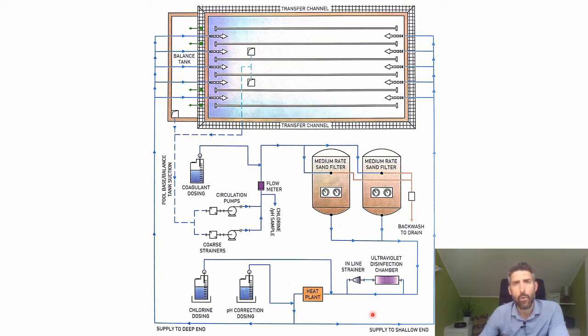A couple of things to note about the UV system itself: the tubes, the lamps, typically will last around 8,000 to 10,000 hours, somewhere in that range, so about a year. The lamps need to be replaced on a yearly basis. Therefore, it will require in most cases a maintenance contract, so there's ongoing costs to it. But an advantage is you'll potentially be able to offset those costs with the reduction in the amount of chemicals that you would have to use.